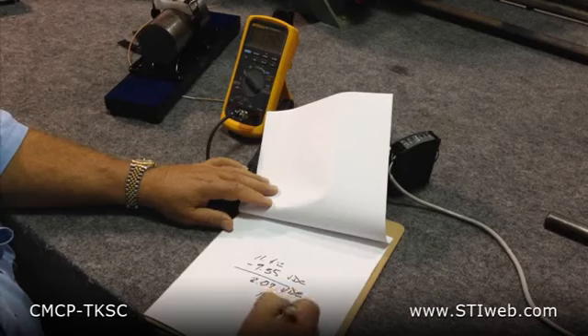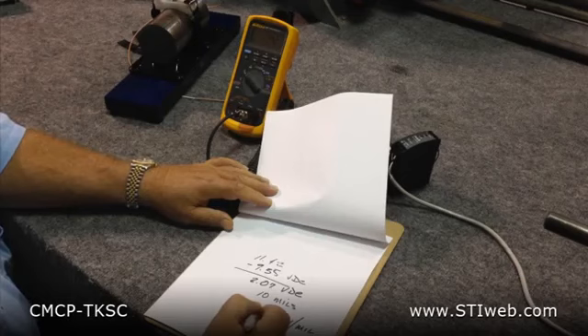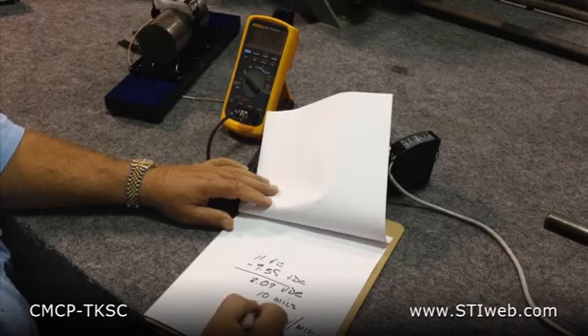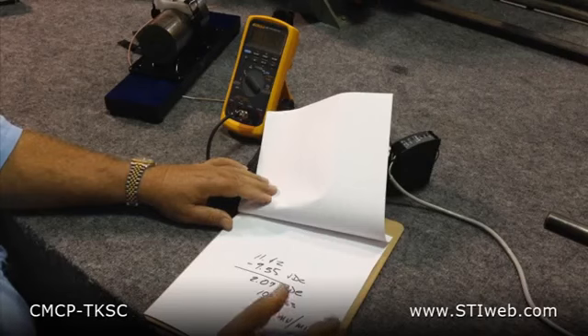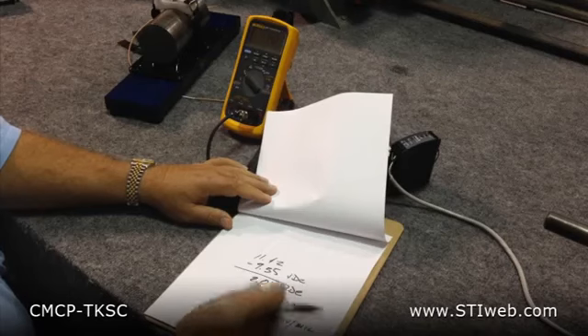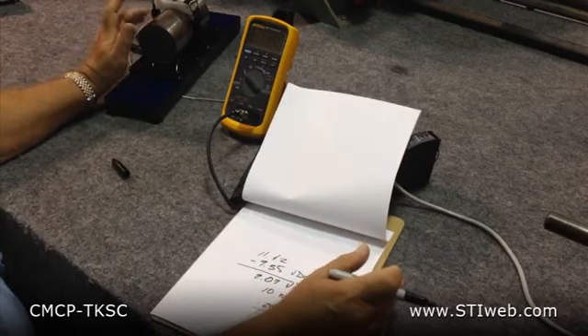0.207 volts per mil, or 207 millivolts per mil. 200 millivolts per mil is standard for API 670 looking at 4000 series steel. Anything from 190 to 210 millivolts would be considered in calibration. So you can tell right now that we're in good shape on this one. If this had been an exotic metal or something we didn't know, or chrome surfaced or something like that, we might have a number as low as 167 or even as high as 237. So it's important to know what your calibration is for an unknown piece of metal. If you know what the metal is, you're in much better shape.